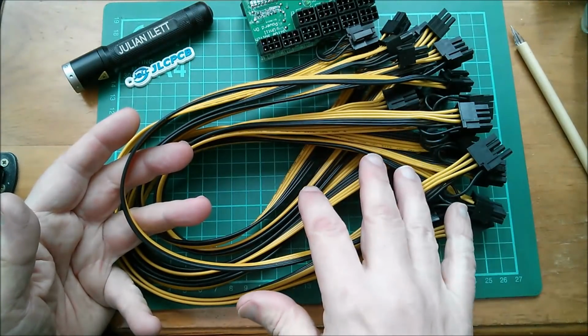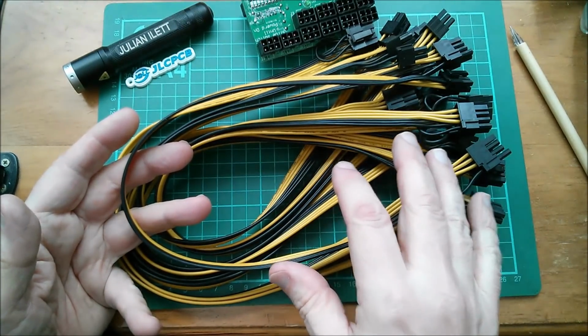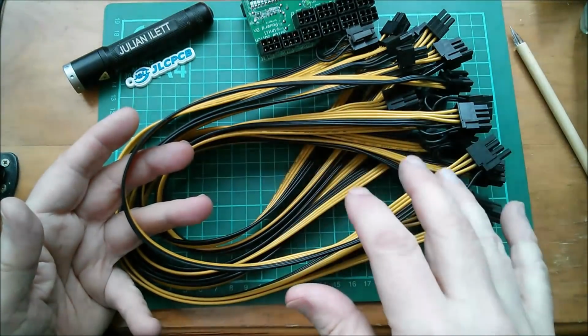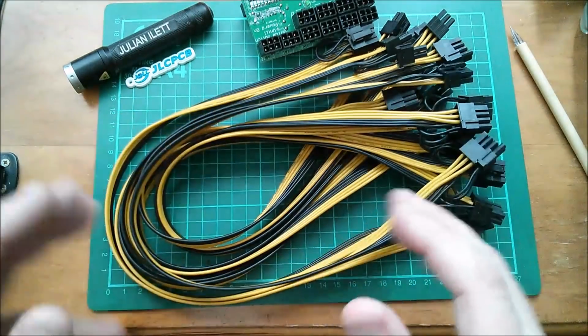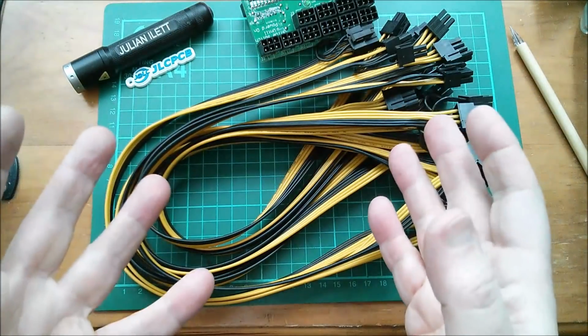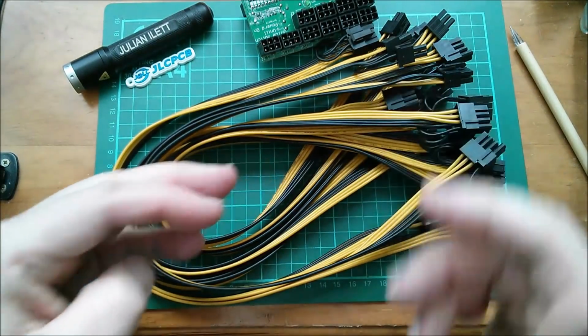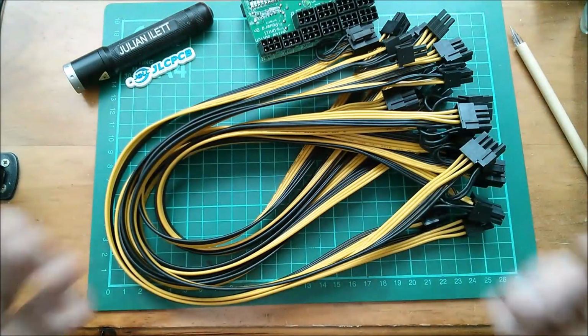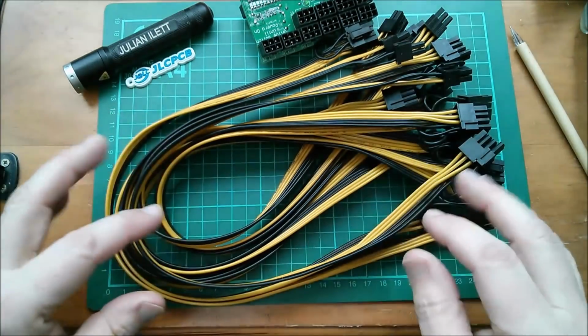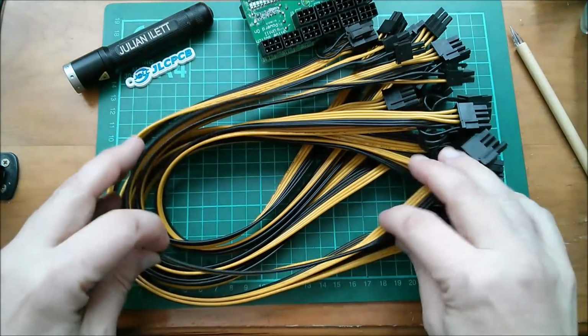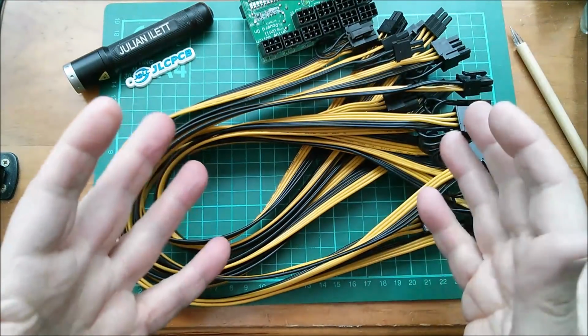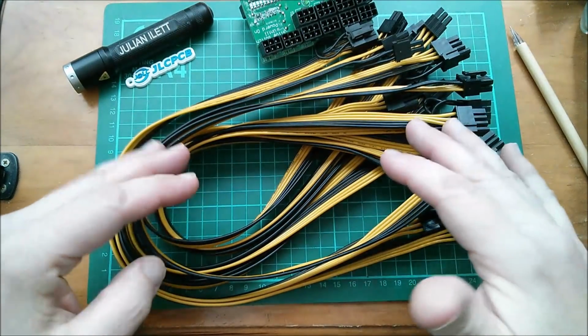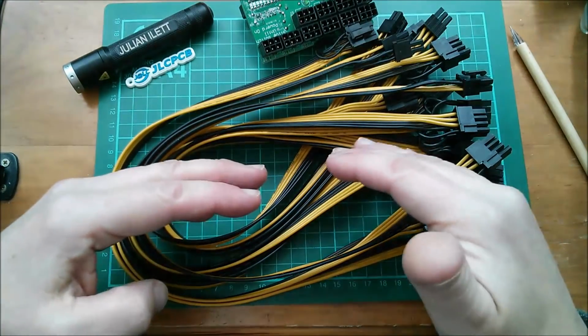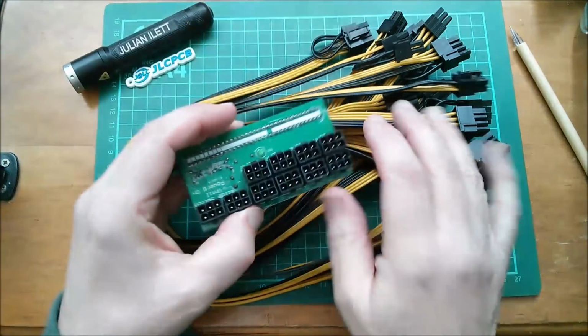The Antminers have a range of voltage. I think it's from 11 to 13 volts. But the trouble is, if my power supply is going to deviate outside of that, I need to do all these tests to see whether those hashing boards will run at a bit more than 13 volts, and I might blow up an Antminer, who knows, whether they'll run at a bit less than 11 volts, in which case I can connect these cables straight to the batteries, or whether I need to use buck boost DC to DC converters to stabilize the voltage at 12 volts, which is what these Antminers run on.